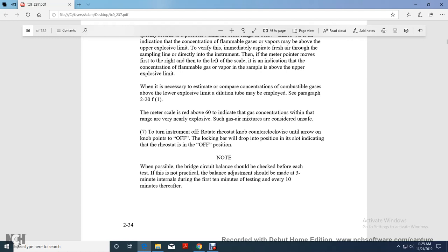When necessary, estimate the concentration of combustible gases above the lower explosive limit; the dilution tube must be employed. Meter scale readings above 60 indicate the gas concentration is within the range and very nearly explosive. Such a gas mixture is considered unsafe. To turn the instrument off, rotate the rheostat knob counterclockwise until the arrow points to off. The locking bar will drop into the slot, indicating the rheostat is in the off position.